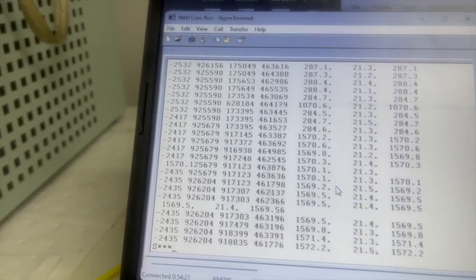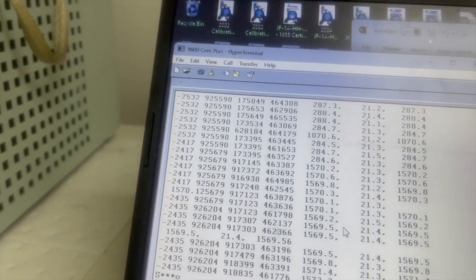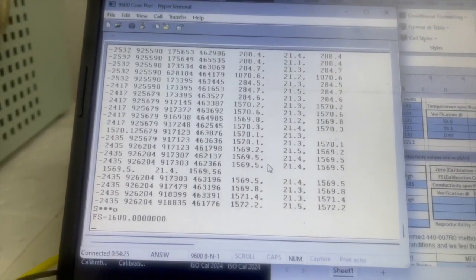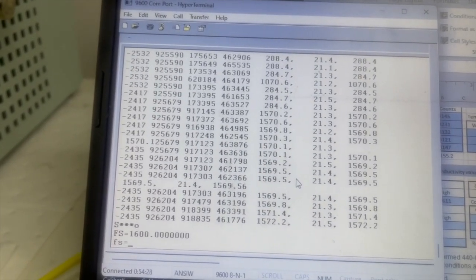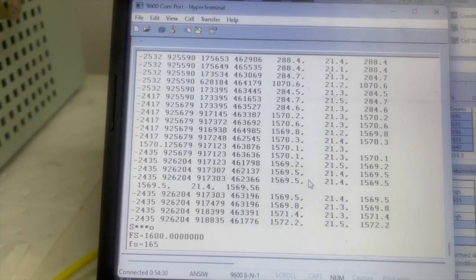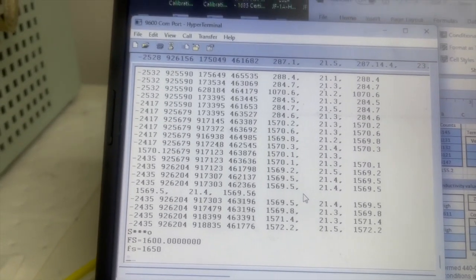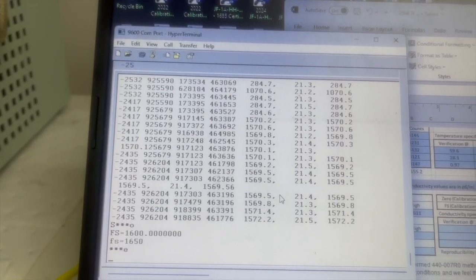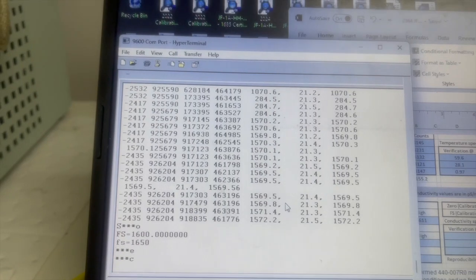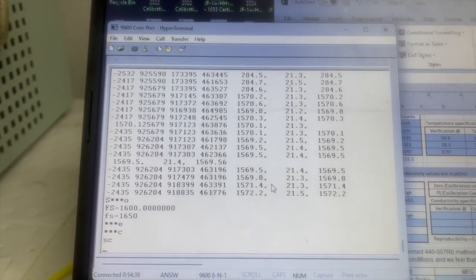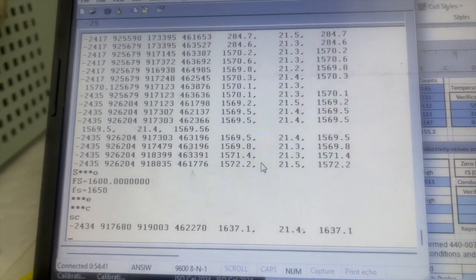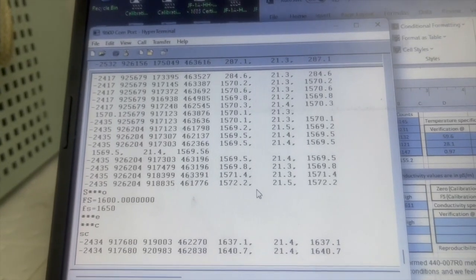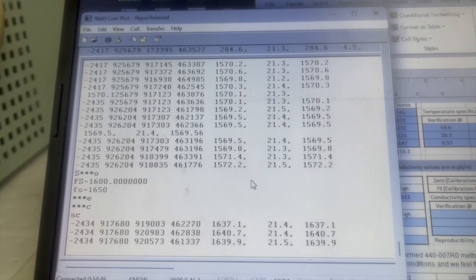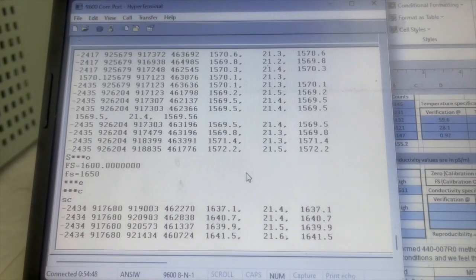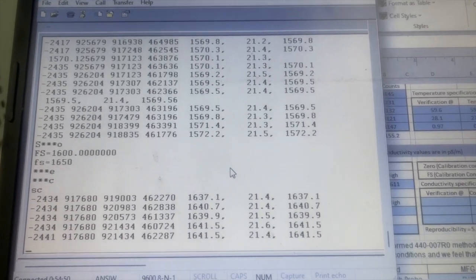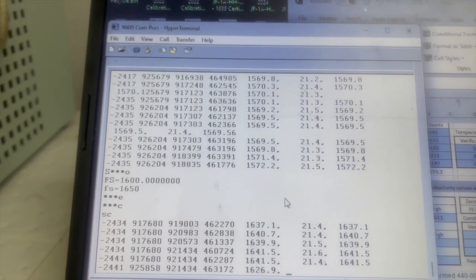Stop. In open mode, full scale set to 1600, so we're going to go full scale equals, we want to go up about 50, I would say. Save it. We're going to go into cal mode and check to see if that's correct. We wanted 1611, and we jumped all the way up to 1641, so that might have been too much of a correction.